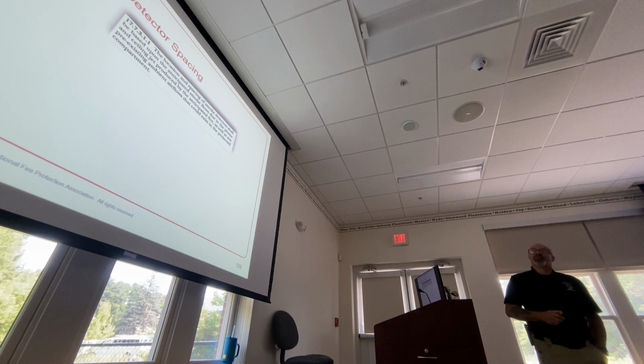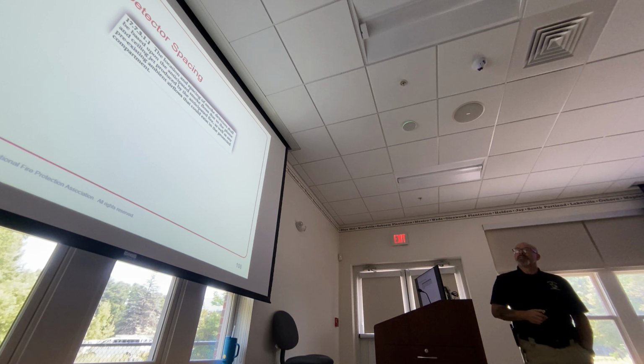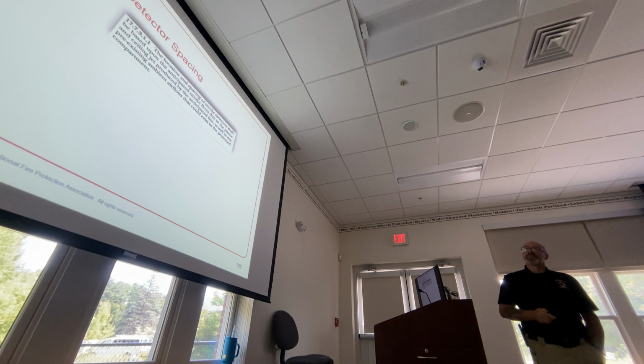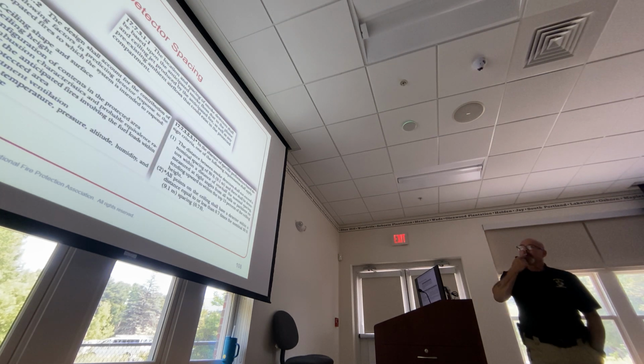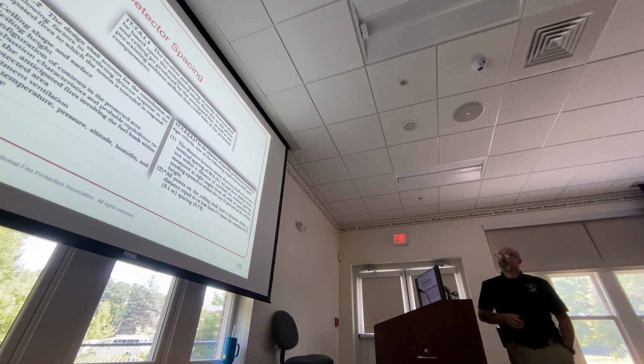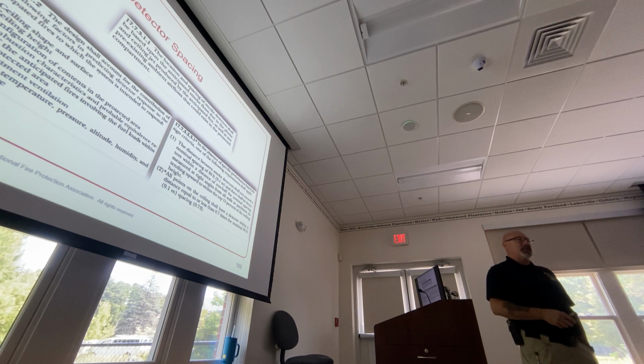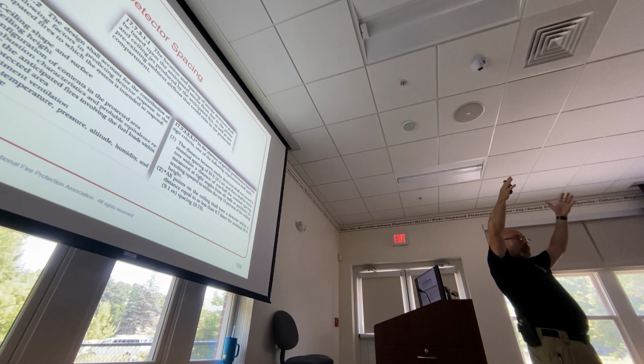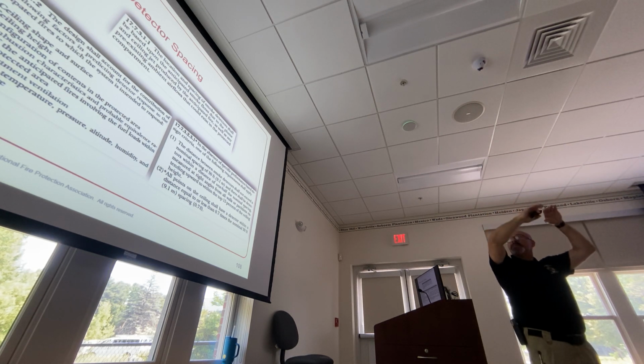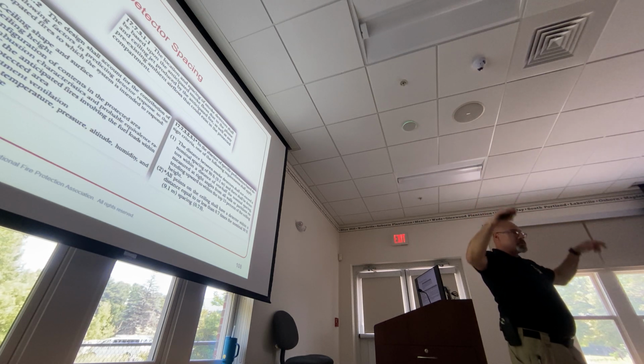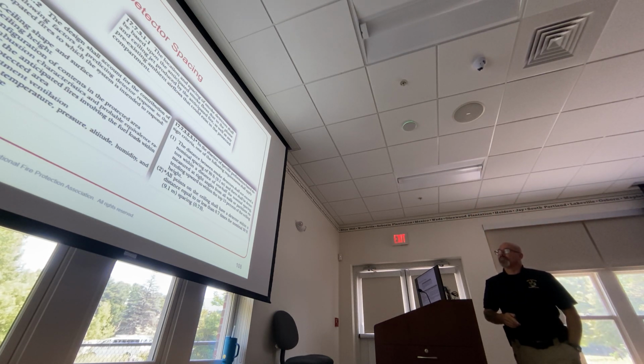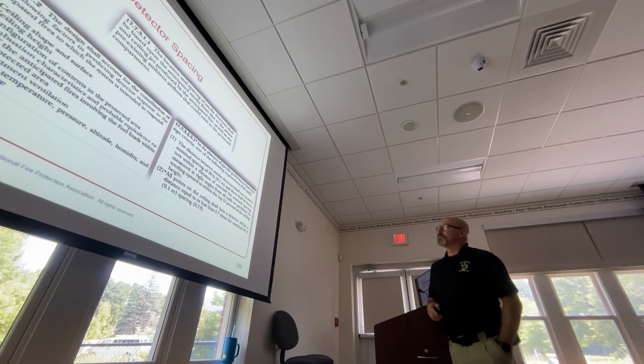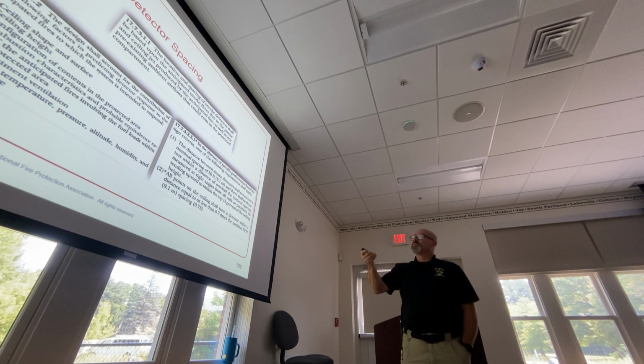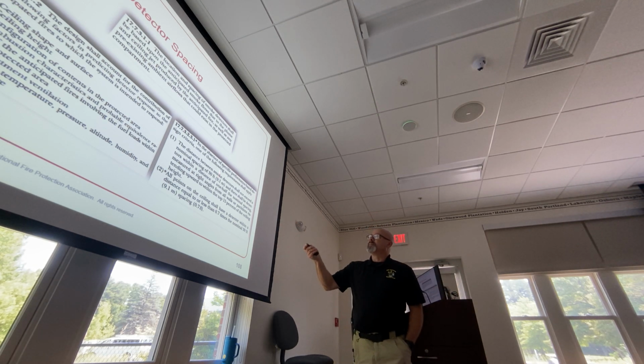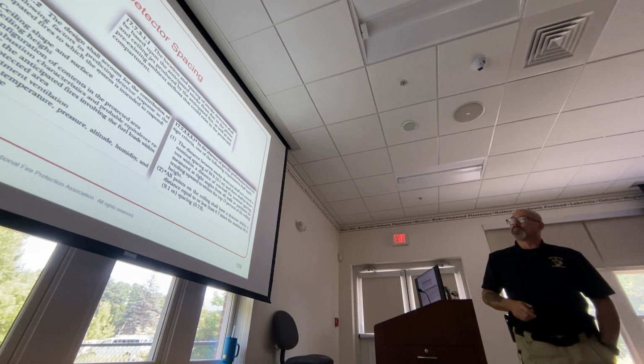Okay, NFPA 72, Chapter 17, 17.7.3.1.1. There's a reason why this is on the board. The location and spacing of smoke detectors shall be based upon the anticipated smoke flows due to the plume and ceiling jet produced by the anticipated fire. The plume is the smoke hitting the ceiling, going up to the ceiling. And the ceiling jet, meaning as it's spreading across the ceiling. As well as any pre-existing ambient airflows that could exist in the protected compartment. That's not so much of a big deal. This may be pretty important for testing purposes.